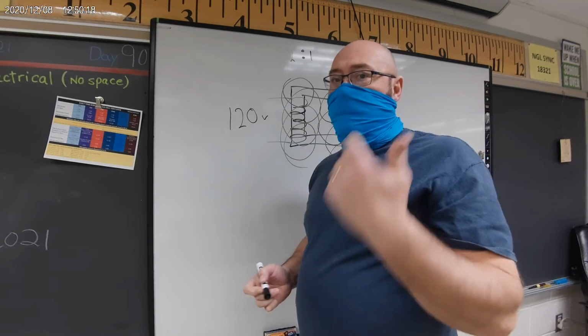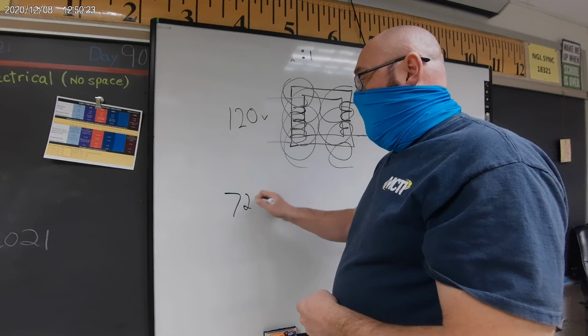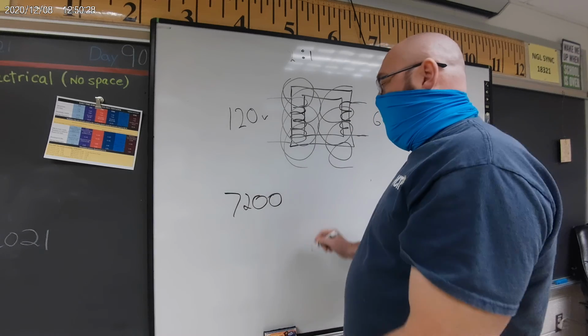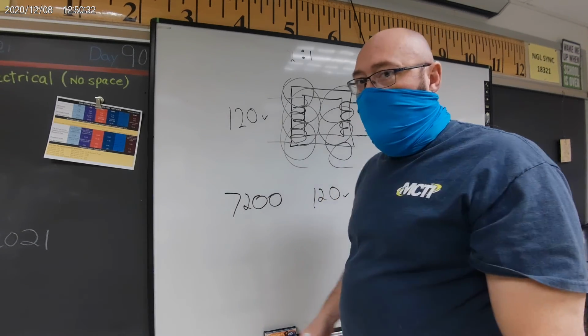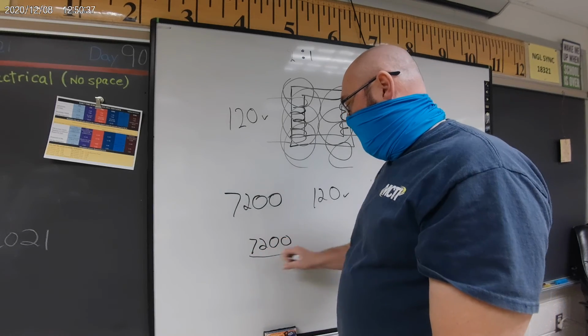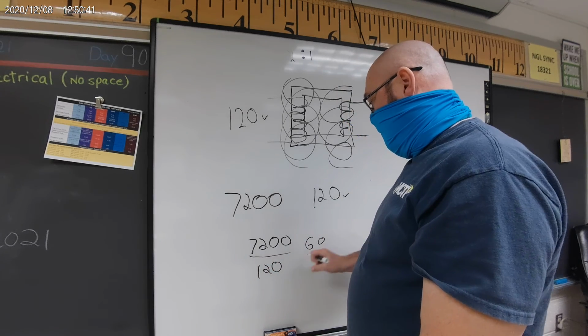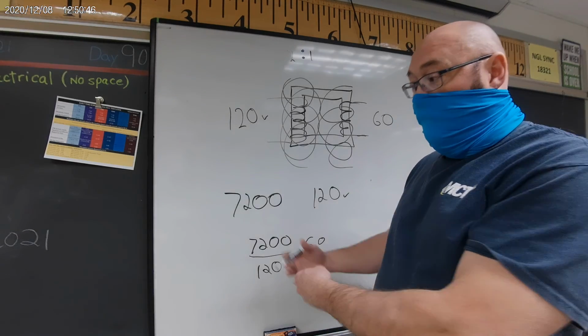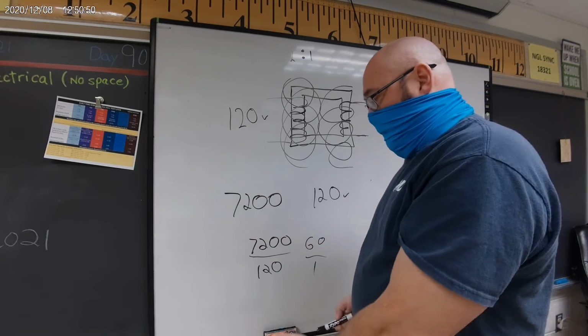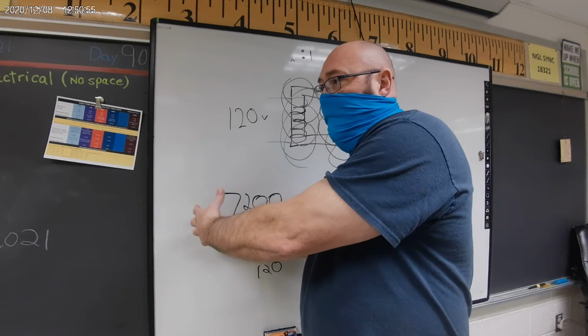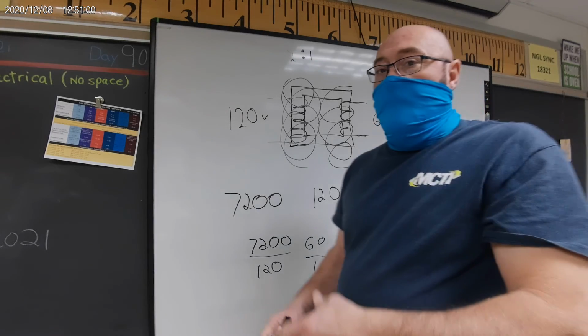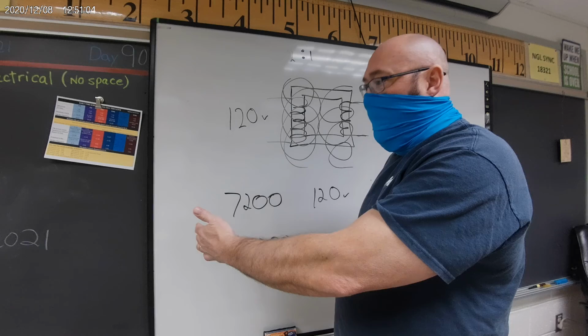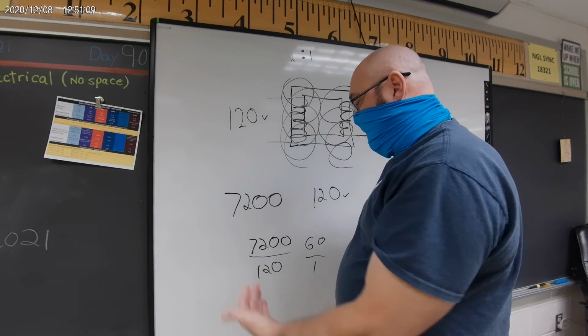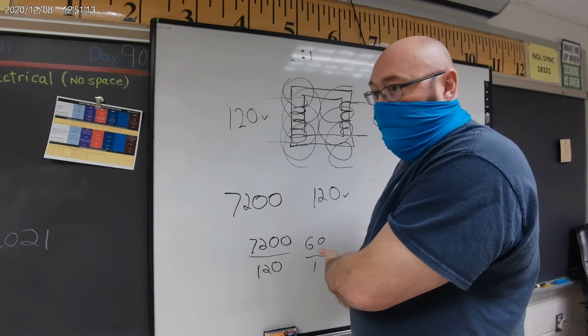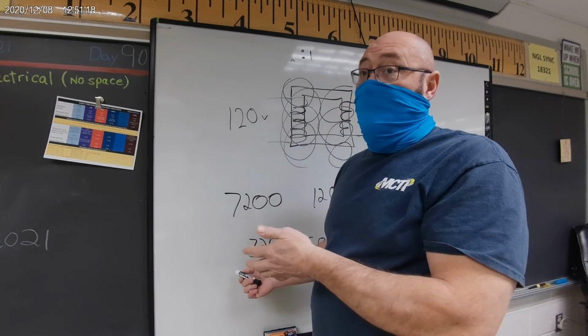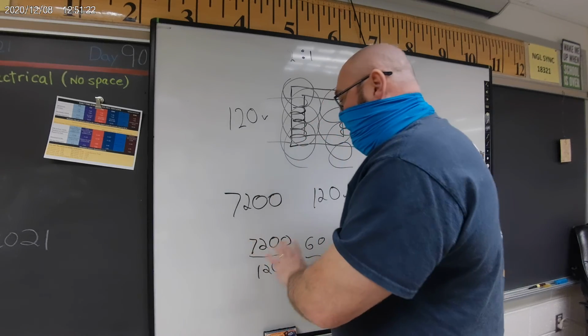So imagine that at your utility pole. That high voltage line coming into the transformer is roughly 7,200 volts, but coming out to my house is 120 volts. So if I do the math over that, that comes out to 60 over 1. So that's a 60 over 1 transformer for the ratio. Everything would be proportional. So for every 60 windings on this side, I only have 1 winding on this side. Now realize there's more than 60 windings. There might be 6,000 windings on the left side, and 1,000 windings on the right. You've got to picture it, it's a lot of windings. But everything is proportional.